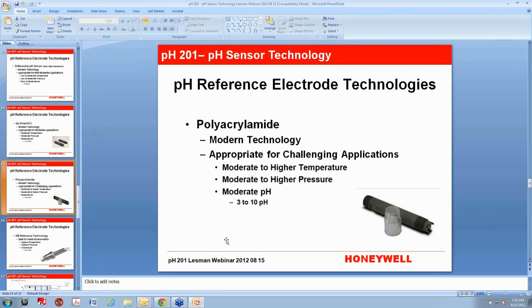And this is a good fill for applications that tend to get into a little bit higher temperatures, a little bit higher pressures, moderate pH, again, 3 to 10. It's still going to have the same issue for chemical attack as the other types of fills, including the double junctions, differential technology, etc. But again, you can see that as time goes on, manufacturers are coming up with technologies that are getting more and more resistant to the terrible things that happen to pH sensors when they get stuck in a process.